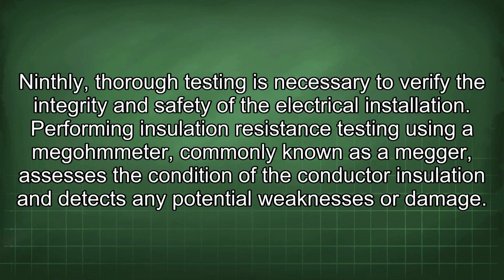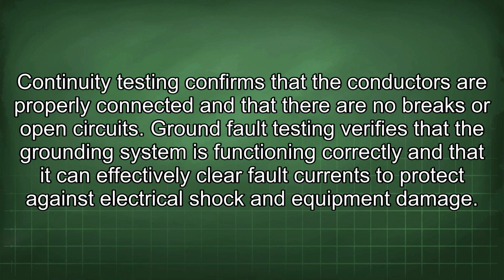Ninthly, thorough testing is necessary to verify the integrity and safety of the electrical installation. Performing insulation resistance testing using a megohmmeter, commonly known as a megger, assesses the condition of the conductor insulation and detects any potential weaknesses or damage. Continuity testing confirms that the conductors are properly connected and that there are no breaks or open circuits. Ground fault testing verifies that the grounding system is functioning correctly and that it can effectively clear fault currents to protect against electrical shock and equipment damage.